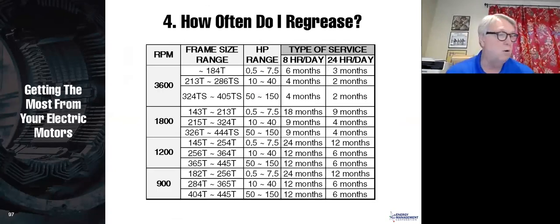Number 4, how often do you re-grease? You can do it by a table. And here's a table. You look at the RPM, the frame size, and then are you running 8 hours a day or 24 hours a day? And it will give you the re-greasing intervals. I think that's not a bad way to do it either. And you can see that most re-greasing intervals run from about 4 to 12 months.